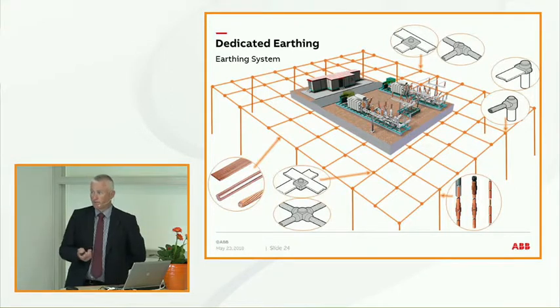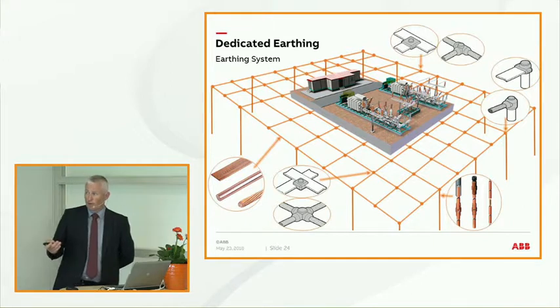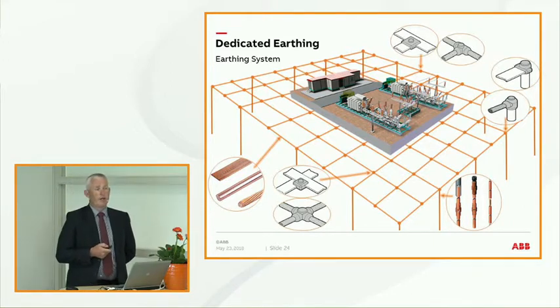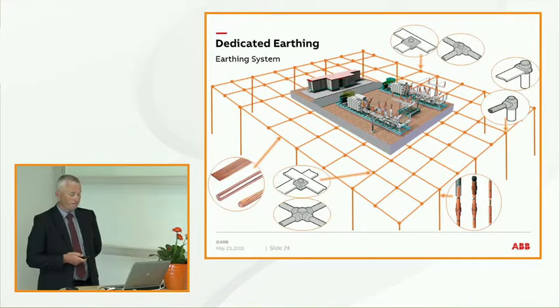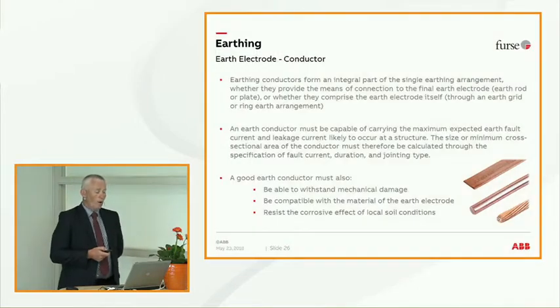It's a permanent joint. Earth electrodes, I'm sure most are familiar with. And the actual conductors, like I say, we opt for copper. I'll explain a little bit later why we go for copper rather than the likes of galvanized steel or stainless steel. When we're looking at earth electrodes, the copper is a better conductor of electricity. It's easy to use. And as you can appreciate, copper's been in the ground for thousands of years. It tends to last in the ground for many, many years. There's no issues with degradation of the materials. This is normally put together through an earth grid or a ring earth arrangement.